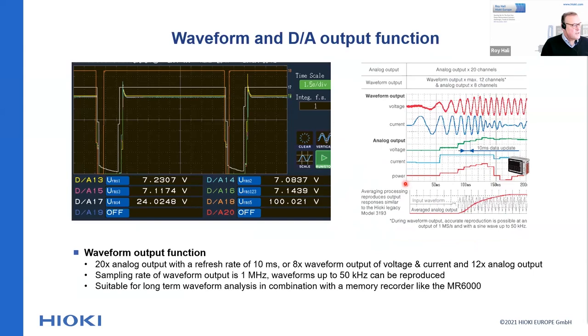The second option that is available on the PW8001 is the waveform and DA output function. This function provides the possibility to output your voltage and current signals in a waveform output with a sampling frequency of 1 megahertz, and it's therefore useful to monitor the shape and the events on your voltage and current signals for a longer time.